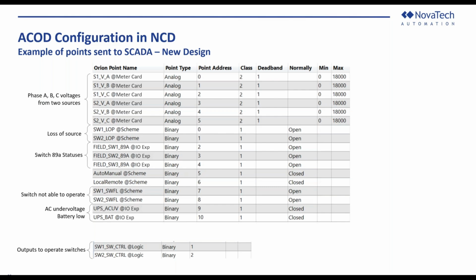Below that, we have the switch statuses, 89A for each of the field switches. Switch 1 is for source 1, switch 2 is for source 2, switch 3 is the bus tie. Then we have the state of the auto manual and local remote of the ACOD. Below that, the switch not able to operate. This is the switch failure that we were talking about for switch 1 and switch 2. And then also for that battery backup system, there's a couple alarm points that we're monitoring as well. Under voltage, or if battery low, also could be that the battery needs maintenance, maybe the battery needs to be replaced.